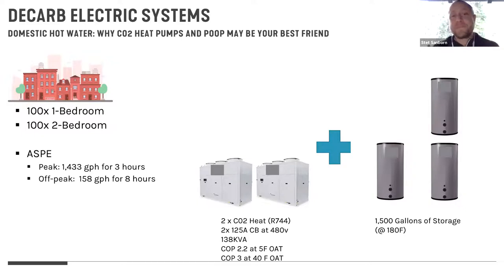So in this particular example, to meet that same load, because I can store water at a much higher temperature, I still distribute at the same temperature, but I can store water at a much higher temperature. I can go down to 2 CO2 heat pumps to meet that same load, and then down to 1,500 gallons of storage. So much smaller footprint, 2 heat pumps instead of 4, and far less actual storage on site. The really nice thing is that same solution, even though it's still an air source heat pump, it's dropping my kVA to 138. So I've reduced that impact on my transformer sizing, which is really, really important because there's dollars in those transformers.